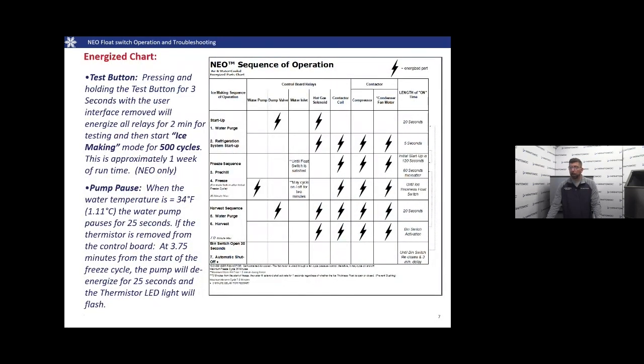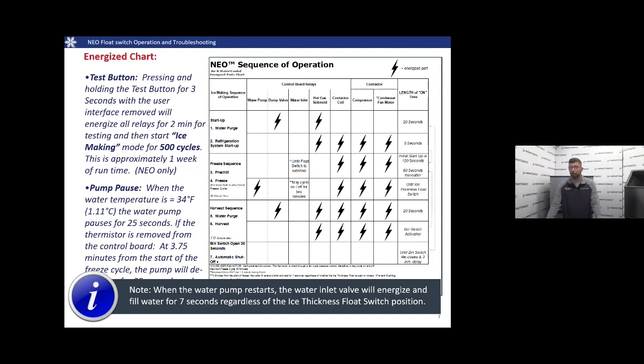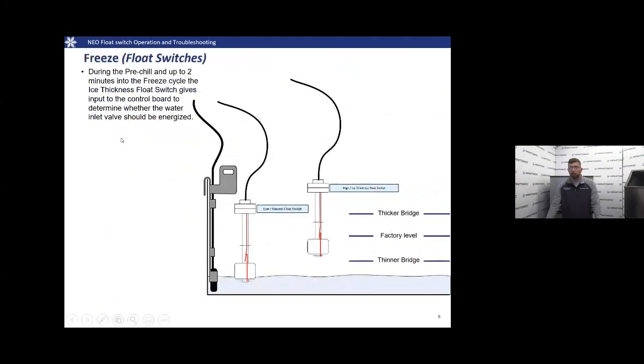This chart shows what the floats are doing throughout the sequence of operations. One thing that can throw people is that pump pause. We utilize the water trough thermistor to pause our pump and bring in fresh water. This is independent of the harvest float switch. So there are times you'll hear from people in the field: the ice thickness float is satisfied but we're still getting a fill. That's normal — that's in our programming. During pre-chill and up to two minutes into the freeze cycle, our ice thickness float is communicating with the board to tell us whether we need water or not. When that float is down during the pre-chill, that sends the signal to the board to fill up with water and the water inlet valve should be energized.